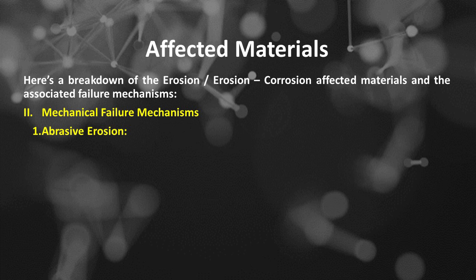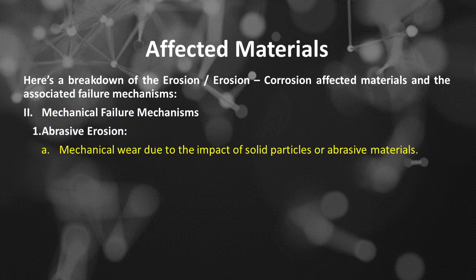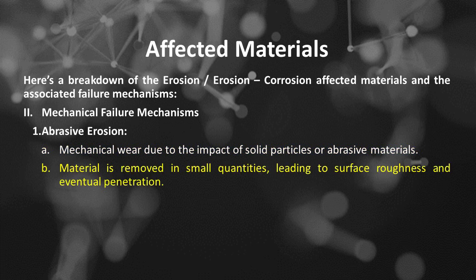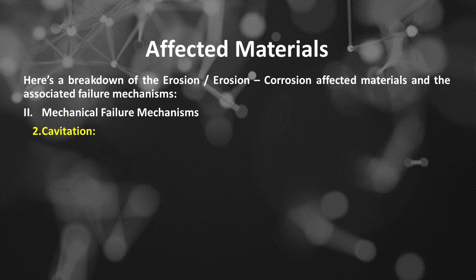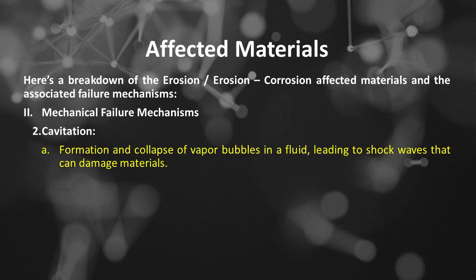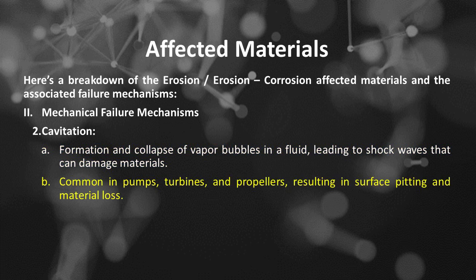Number 1 is abrasive erosion, including: The first is mechanical wear due to the impact of solid particles or abrasive materials. The second is material removed in small quantities, leading to surface roughness and eventual penetration. Number 2, from the mechanical failure mechanisms point of view, is cavitation, including: The first is formation and collapse of vapor bubbles in a fluid, leading to shock waves that can damage materials. The second is common in pumps, turbines, and propellers, resulting in surface pitting and material loss.